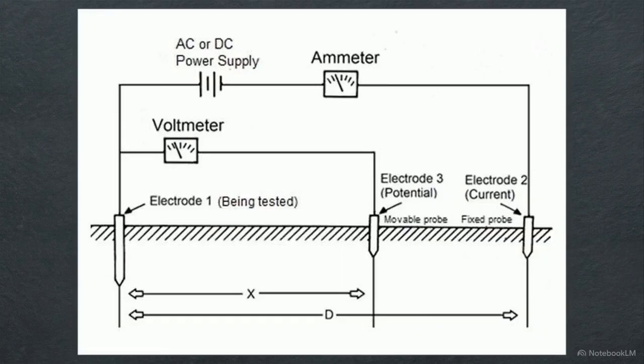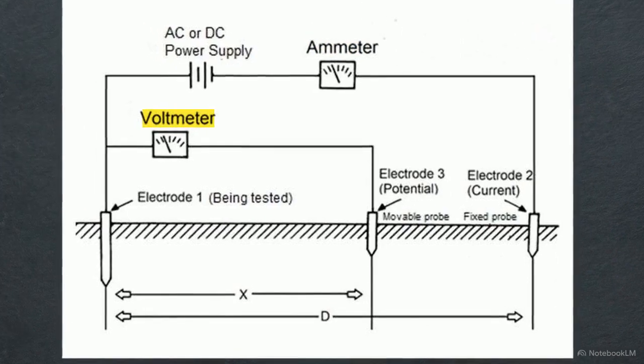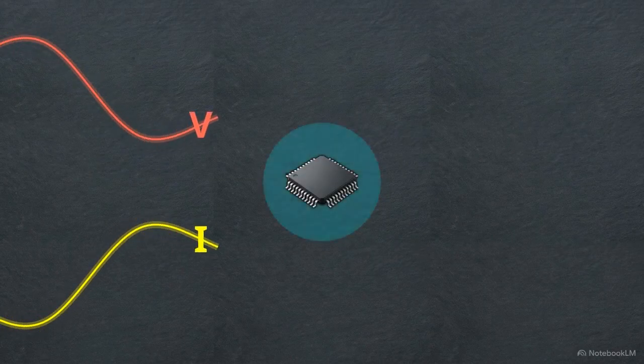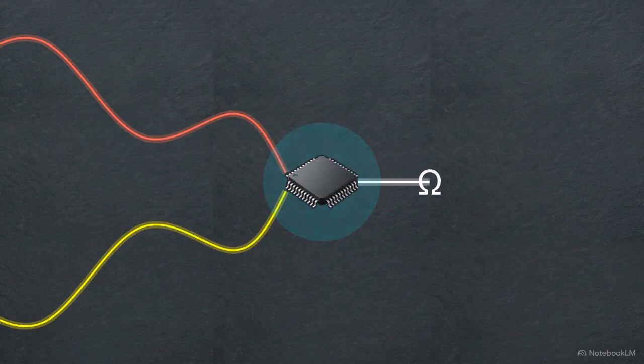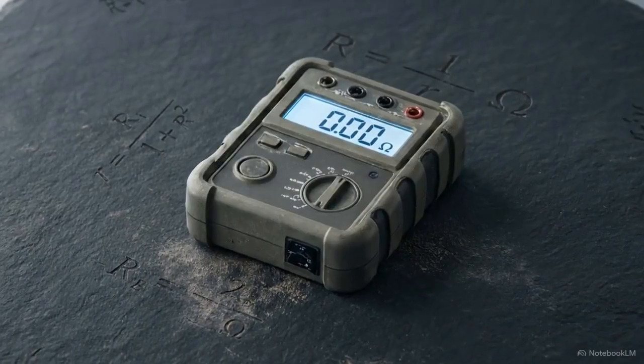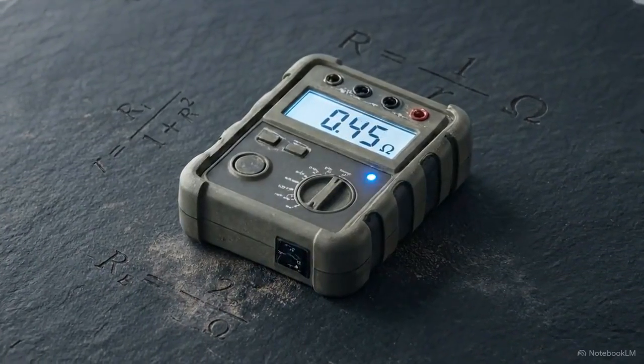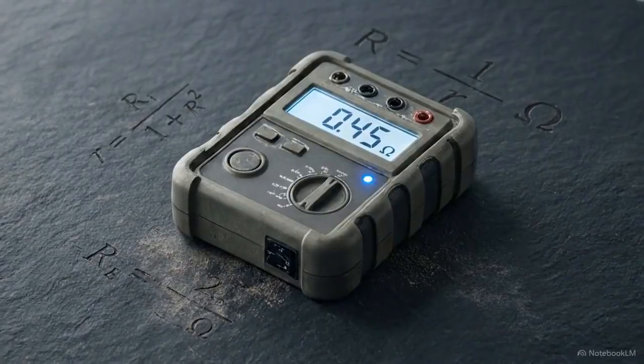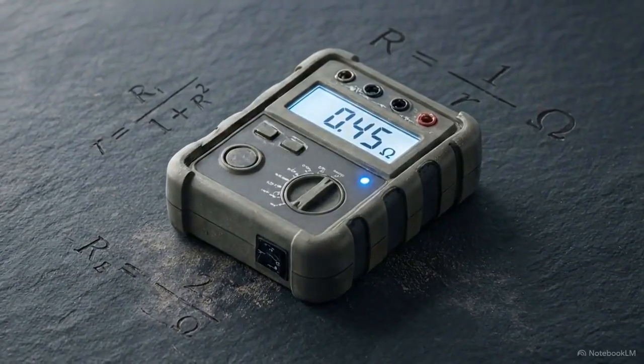The internal schematic reveals how the earth tester processes data. Powered by an AC or DC supply, an ammeter tracks current across the outer loop from electrode 1 to 2. Simultaneously, a voltmeter connects to movable electrode 3, measuring the soil's potential difference. The device then calculates the final value using Ohm's law. Resistance equals voltage divided by current. This direct mathematical relationship forms the basis of electrical safety verification, converting raw voltage and current readings into actionable proof of compliance.